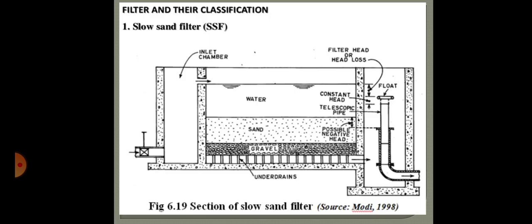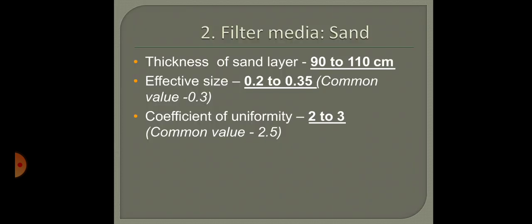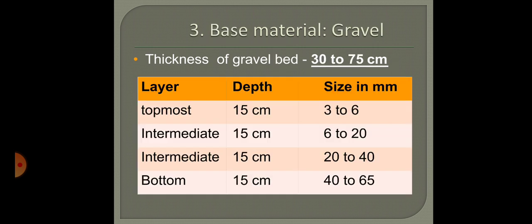For the filter media, we normally use sand. The depth or thickness of the sand media is kept between 90 to 110 centimeters. The effective size of the sand varies from 0.2 to 0.35 mm, and the coefficient of uniformity is between 2 to 3.